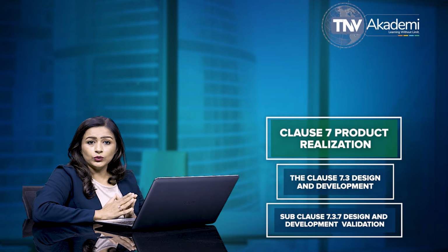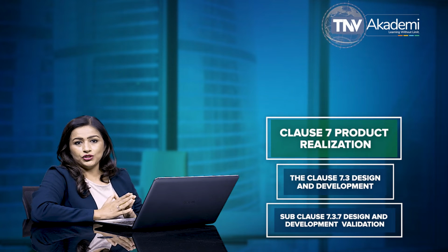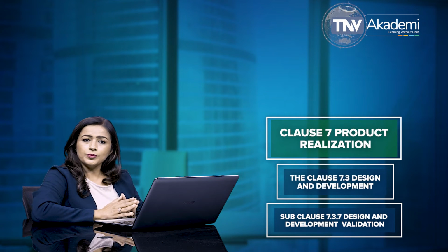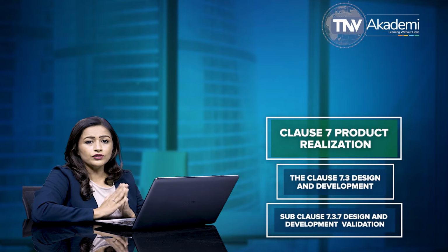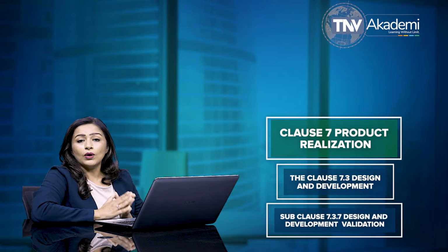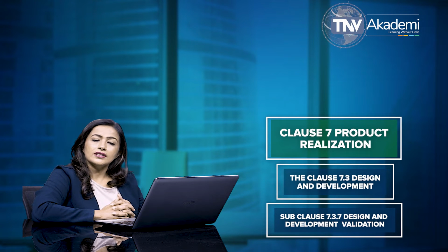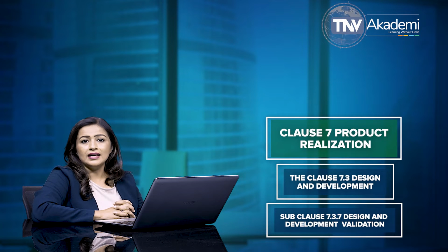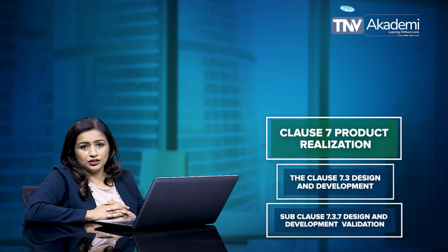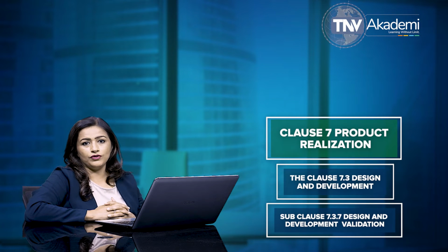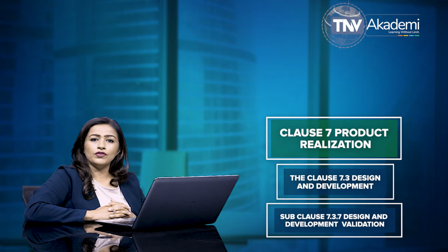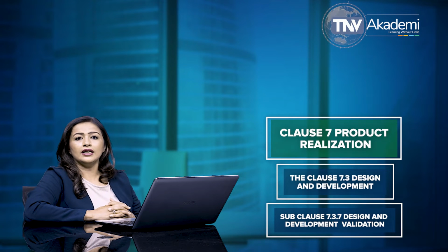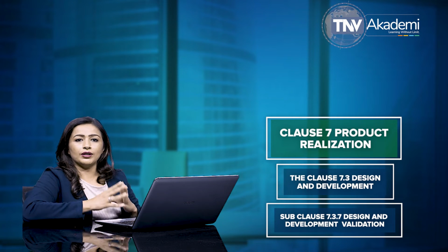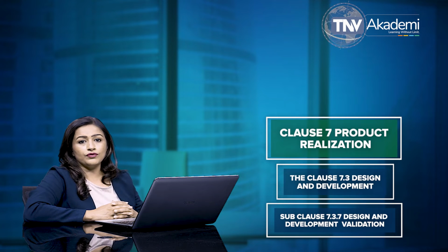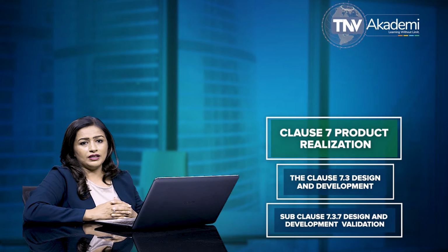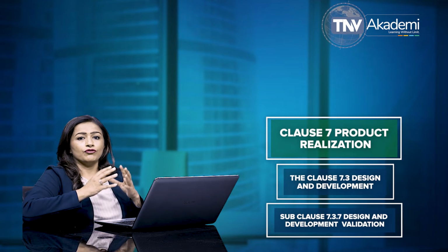Representative product includes initial production units, batches, or their equivalents. As per the clause, the rationale for the choice of product used for validation is required to be recorded. The clause 7.3.7 specifies that as part of design and development validation, the organization is required to perform clinical evaluations or performance evaluations of the medical device in accordance with applicable regulatory requirements. A medical device used for clinical evaluation or performance evaluation is not considered to be released for use to the customer.